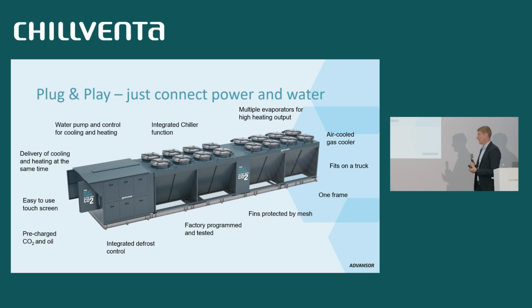Then we have, as I said, everything is factory tested, factory programmed. The defrost control is integrated. So it's actually just to connect water and electricity, and then we can run the heat pump. We even perform evacuation of the system, pre-charged with oil, pre-charged with a small amount of CO2. So when it comes on site, it's just to add more CO2, and then you're ready to start up. Then we also have water pumps, both on the hot side and the cold side, so we can ensure the right supply temperature. Then we have a touch panel at the front of the electrical panel, so it's easy for service and monitoring. Even a cloud-based solution is possible. So it's really easy to use, easy to service the unit.